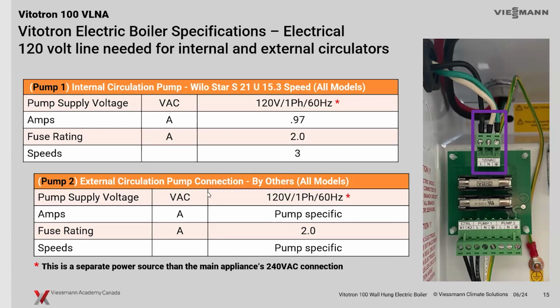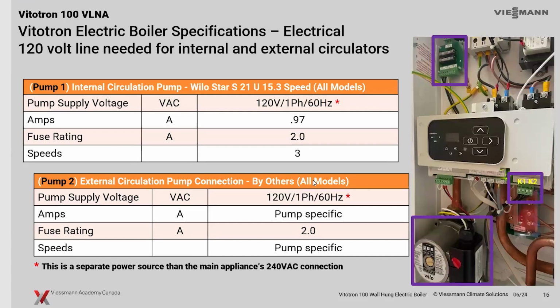And you also have another pump output here that's available, pump 2, should you require a second pump output for, say, primary, secondary, or whatever you might look at. As far as operation of this, there is a fuse protection on that little board, but the power goes through a little contactor here. There's actually a little pump relay built into the unit here.